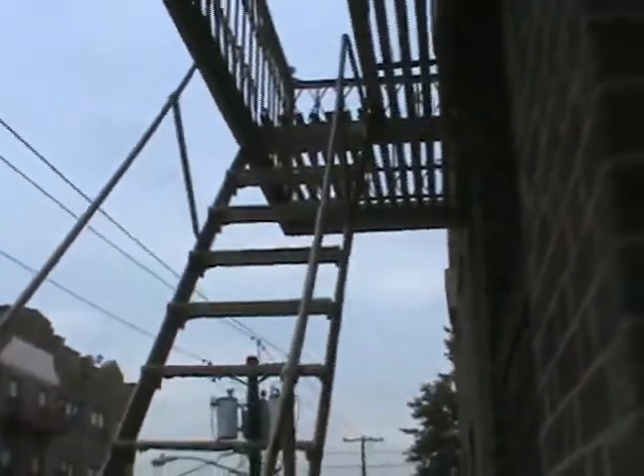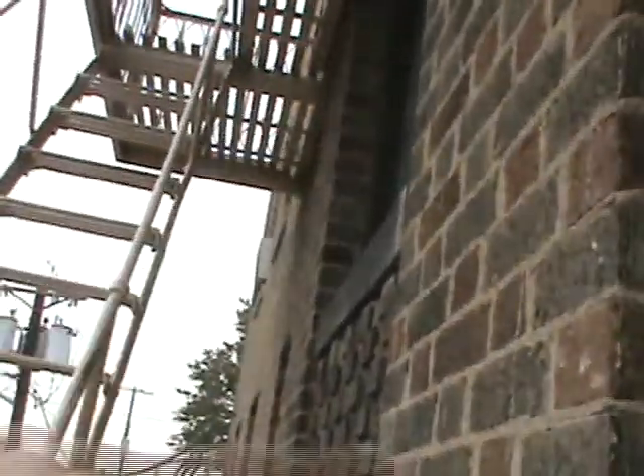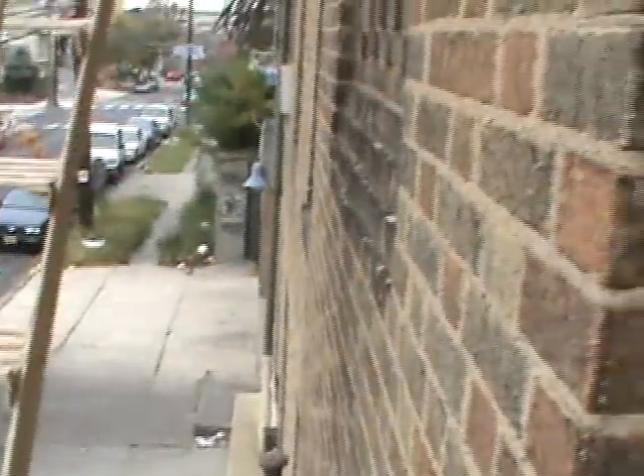And again, any and all work that involves modification to a fire escape will need drawings, engineer oversight, permits. This fire escape does have a need for major structural work. A lot of the cement work on this building is an issue, every single one of the cement. And again, from the other fire escapes we've already examined, I'm going to show you the cause. One of the corners is already spalling, an entire, what I would call a main support on this fire escape. So as we go up, I'll show you what that looks like.